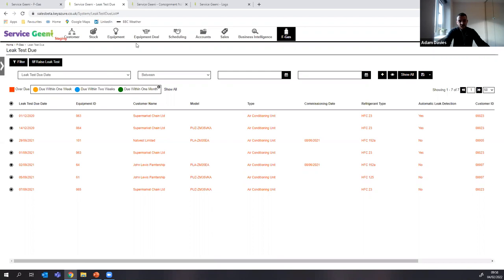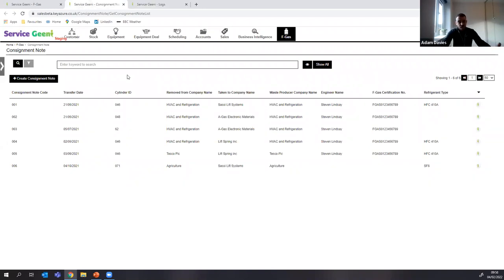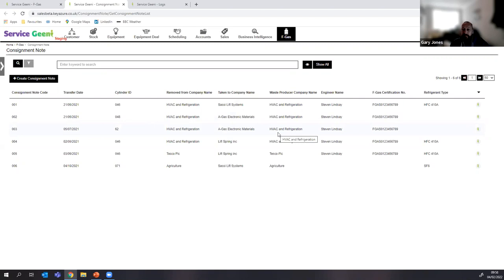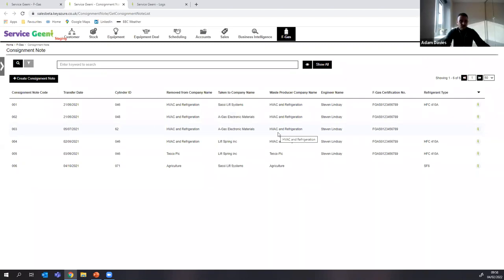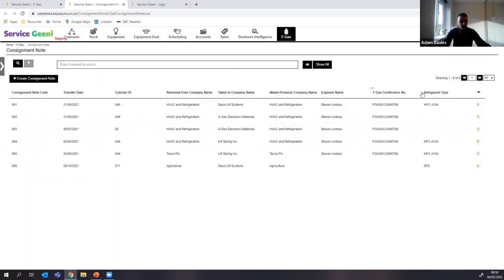To cover the last two areas — Consignment Notes are essentially waste transfer notes, listing where gas has been removed from and where it's been taken. These populate a certificate. It's another part of the audit trail, covering the management of waste gas. This is a really important part of the audit process — a regulatory agency could arrive and ask to see where waste gas has gone. The record shows who did it, their FGas certification number, refrigerant type, cylinders, and dates.